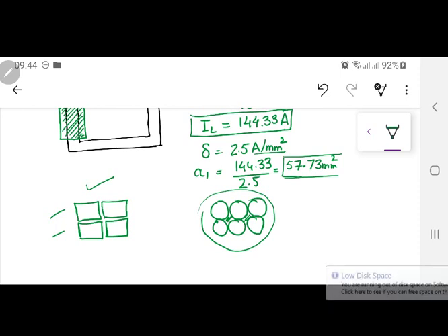And since the currents which are going to flow inside this winding are going towards your fans, maybe your laptop chargers, mobile chargers or whatever, they are going to be rich in harmonics. You don't know what type of load the 100 kVA transformer is going to be loaded with. Rarely is it a first fundamental; it's always going to be third harmonic, fifth harmonic, seventh harmonic and so on. So what will happen over there? There is going to be skin effect also taking place inside your conductor. And you are already familiar with the skin effect.